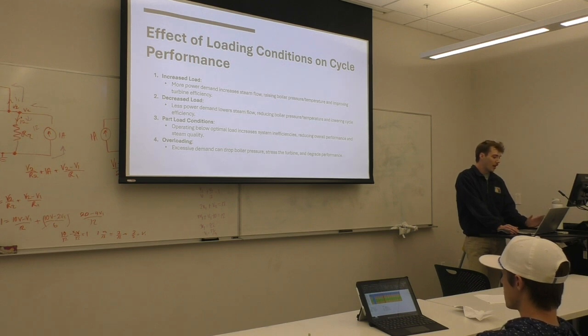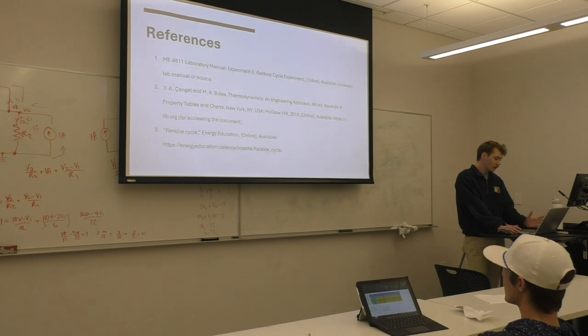If we operate below the optimal load, it increases the system's inefficiencies, reducing overall performance and steam quality. And then lastly, overloading, which is our excessive demand that can drop the boiler pressure, stress the turbine, and degrade performance. And lastly, my references.